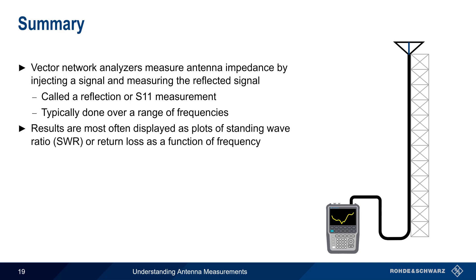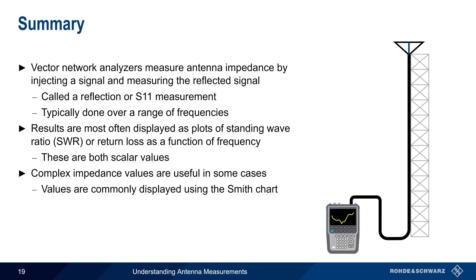The results are most often displayed as a plot of standing wave ratio or return loss as a function of frequency, and both of these are scalar, that is, magnitude only measurements. In some cases, such as when designing matching networks, complex values are also useful, and these are usually displayed in the form of traces on a Smith chart, with markers used to read off specific values.